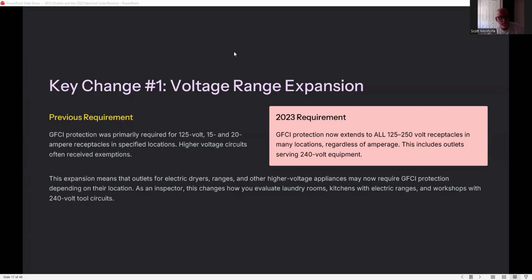So, key change number 1, voltage range expansion. Previous requirement: GFCI protection was primarily required for 125 volt, 15 and 20 amp receptacles in specified locations. Higher voltage circuits often received exemptions. The 2023 requirement: GFCI protection now extends to all 125 to 250 volt receptacles in many locations, regardless of amperage. This includes outlets serving 240 volt equipment. This expansion means that outlets for electric dryers, ranges, and other high voltage appliances may now require GFCI protection depending upon their location. As an inspector, this changes how you evaluate laundry rooms, kitchens, electric ranges, workshops with a 240 volt tool circuit.